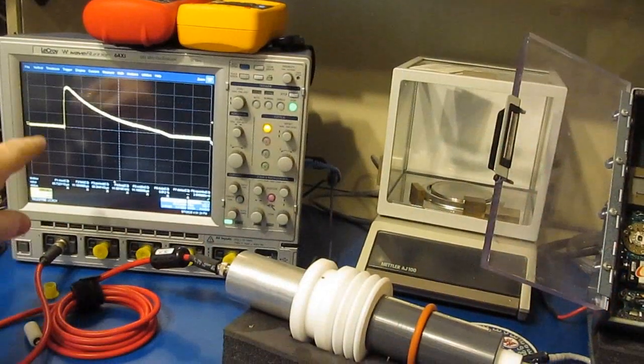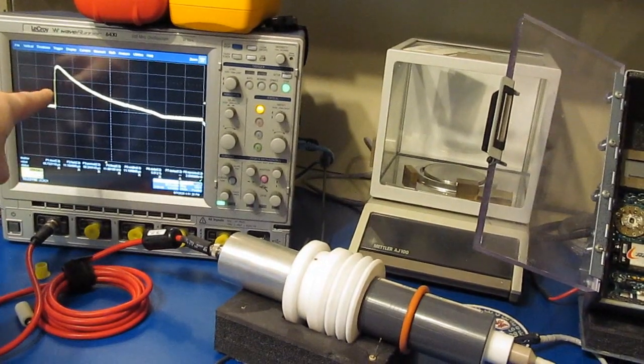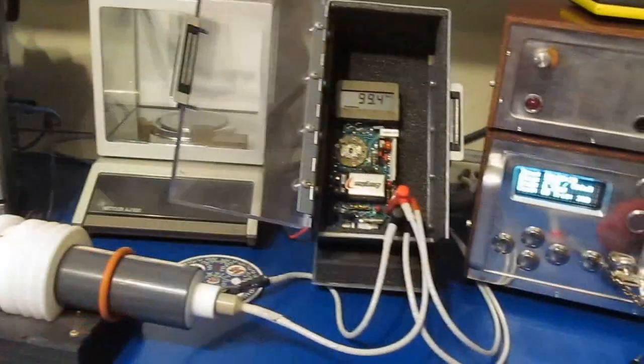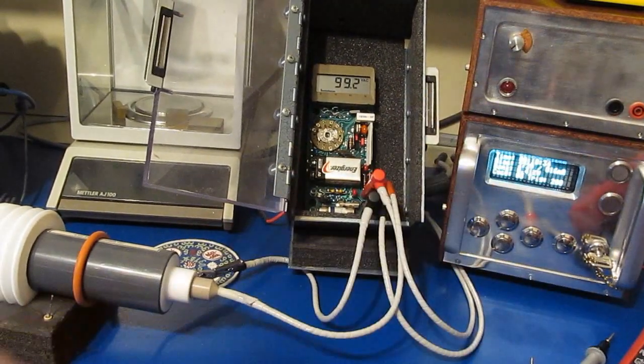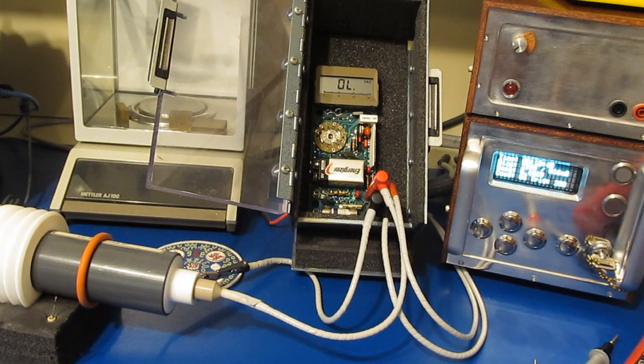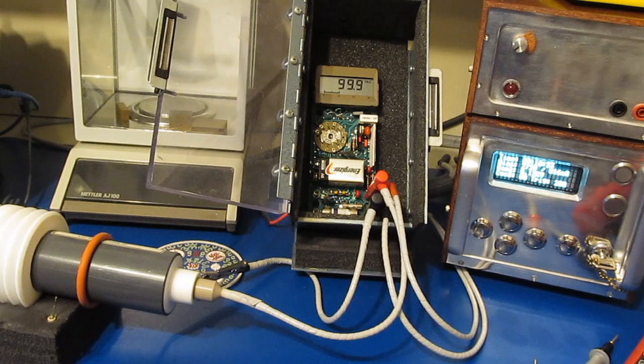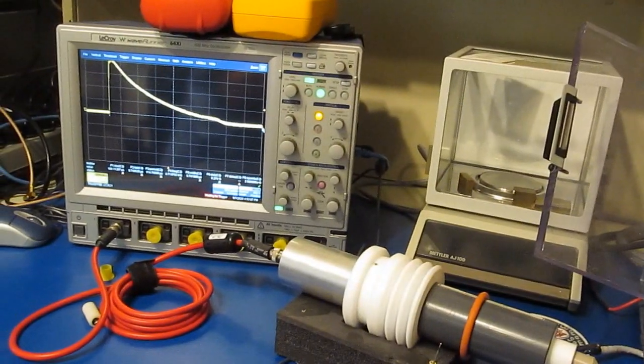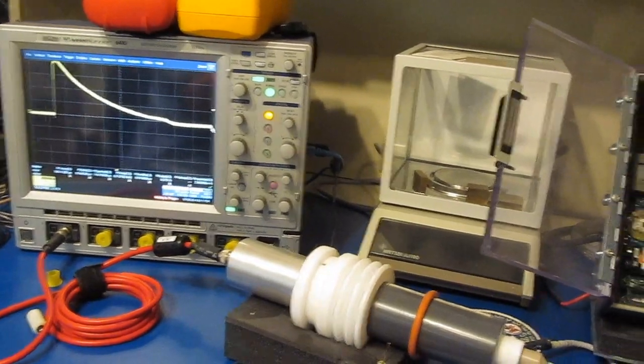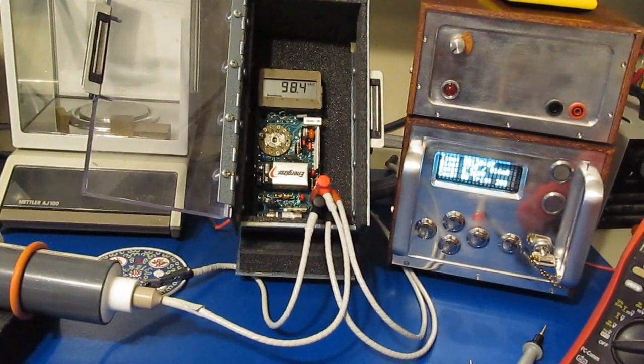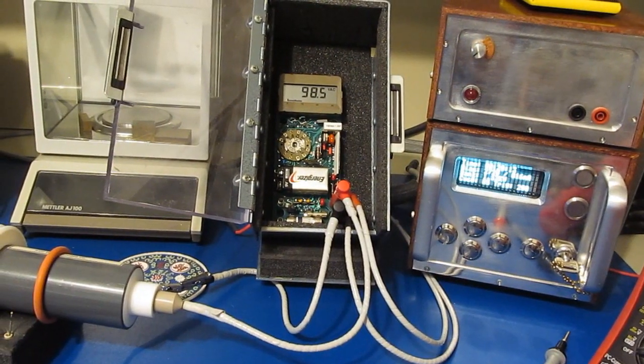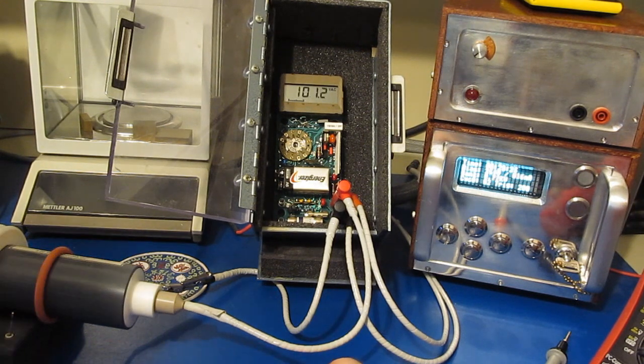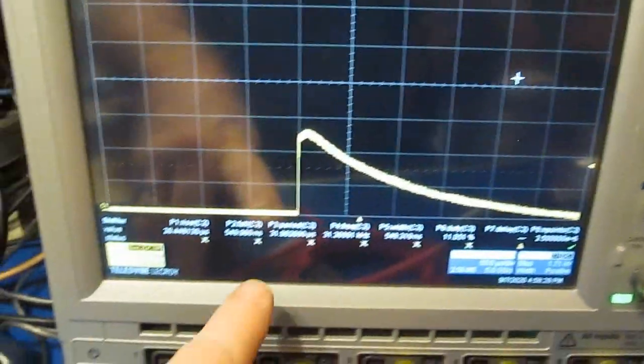You can see we are now three divisions up times 500 volts, or roughly 1.5 kV peak. Again, we'll be applying five positive transients. It looks like it's holding up just fine. And here you can see we're now four divisions or 2,000 volts peak.